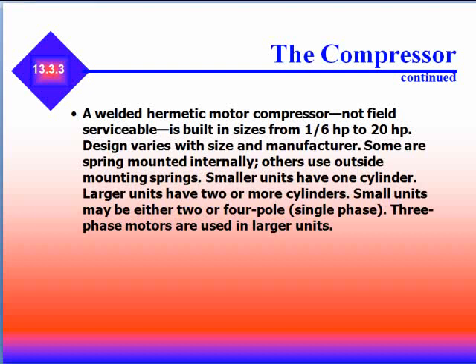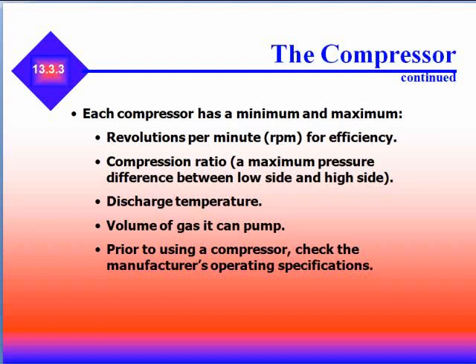Some compressors are spring mounted internally; others use outside mounted springs. Smaller units have one cylinder, larger units have two or more cylinders. Small units can be two or four pole single phase, while three-phase motors are used in larger units. Each compressor has a maximum and minimum RPM for efficiency.